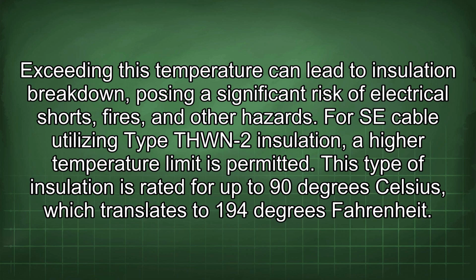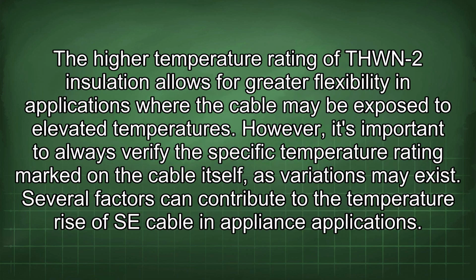hazards. For SE cable utilizing type THWN-2 insulation, a higher temperature limit is permitted. This type of insulation is rated for up to 90 degrees Celsius, which translates to 194 degrees Fahrenheit. The higher temperature rating of THWN-2 insulation allows for greater flexibility in applications where the cable may be exposed to elevated temperatures.